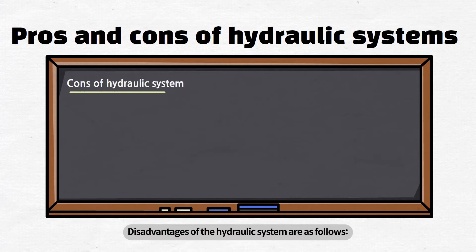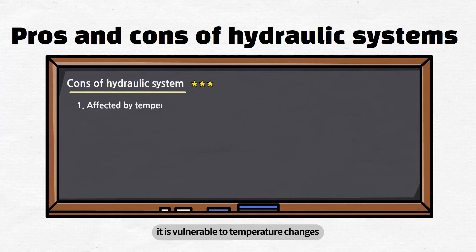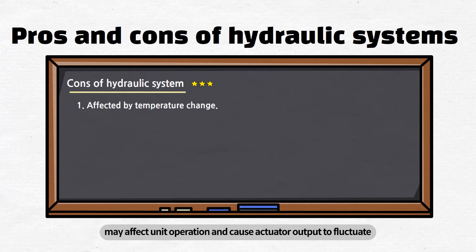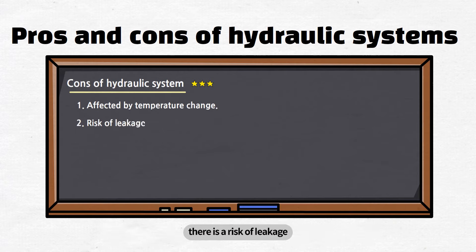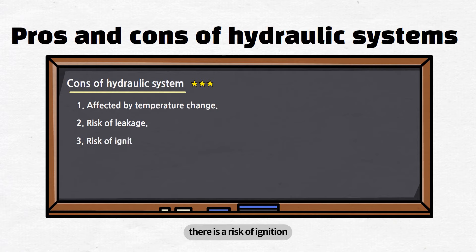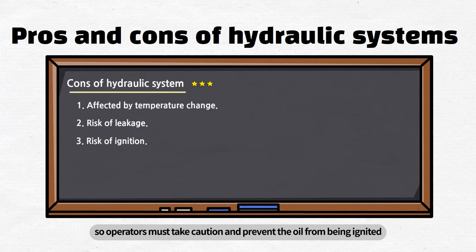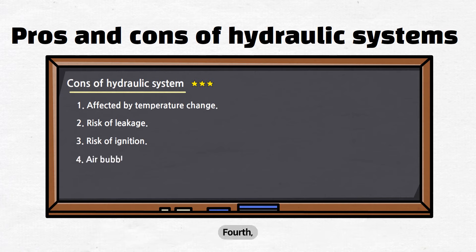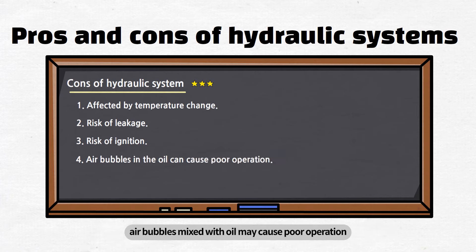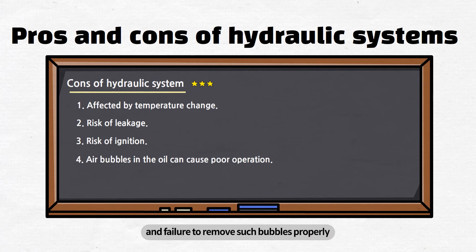Disadvantages of the hydraulic system are as follows. First, it is vulnerable to temperature changes. Viscosity decreased due to temperature changes may affect unit operation and cause actuator output to fluctuate. Secondly, there is a risk of leakage. Third, there is a risk of ignition — the working fluid is oil, so operators must take caution and prevent the oil from being ignited. Fourth, air bubbles mixed with oil may cause poor operation. Oil circulation may form small bubbles, and failure to remove such bubbles properly may result in poor operation of the actuator.